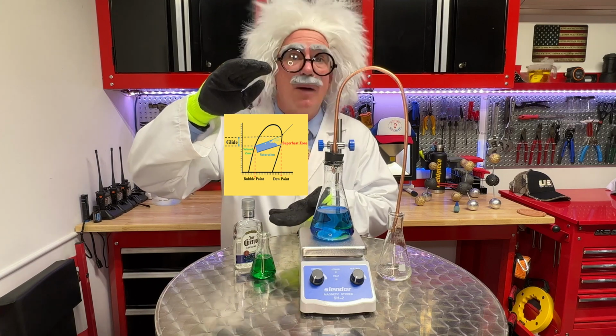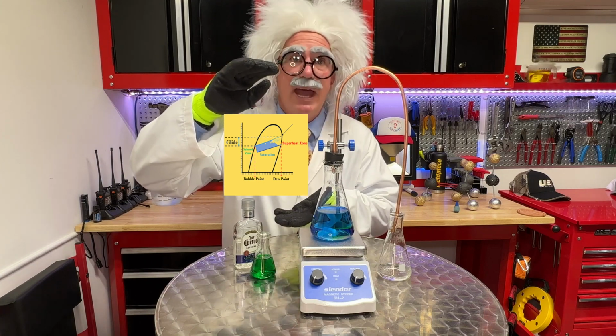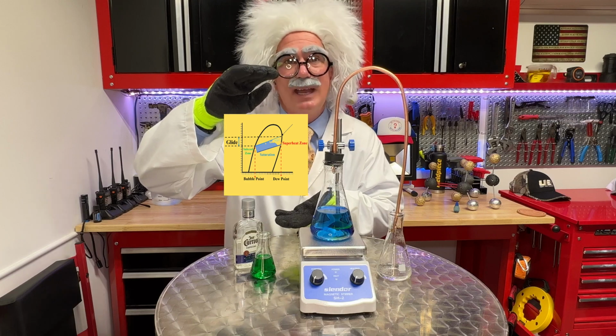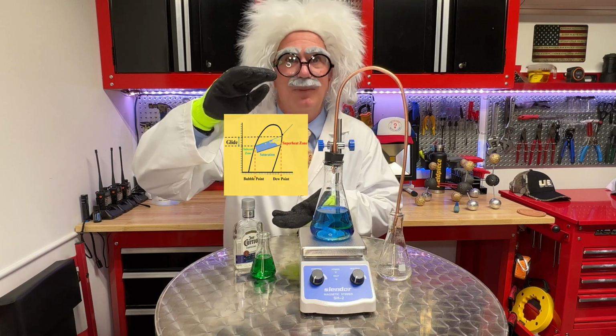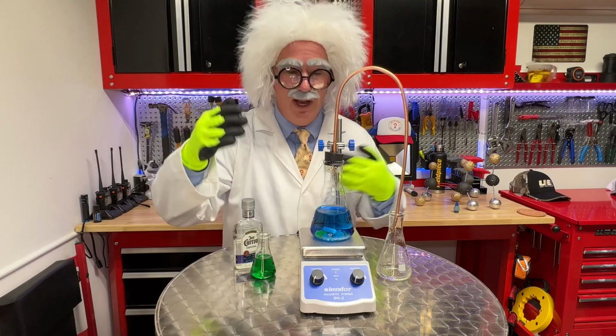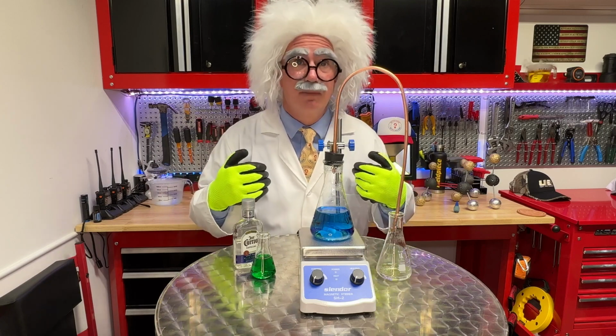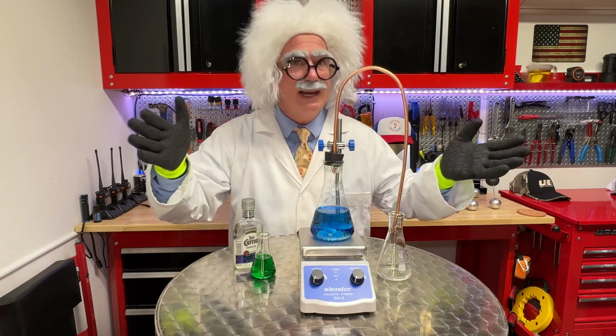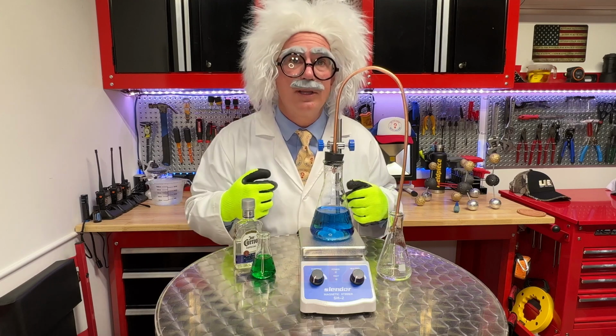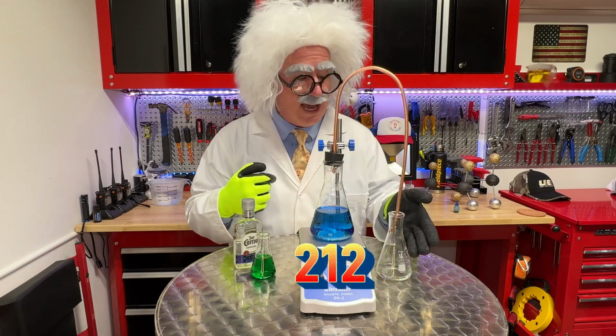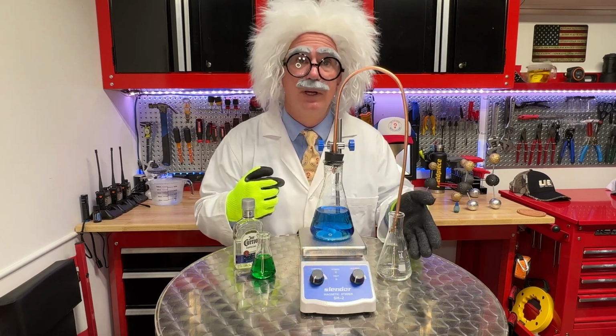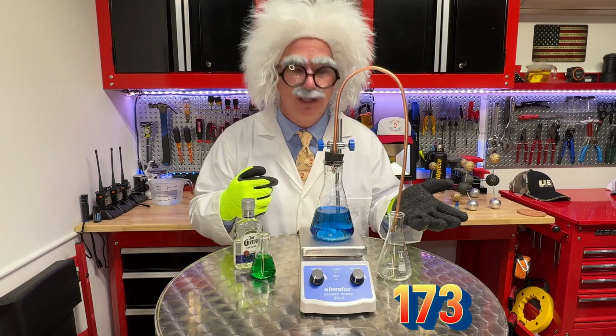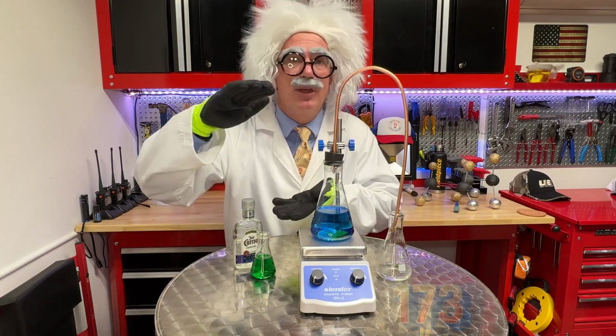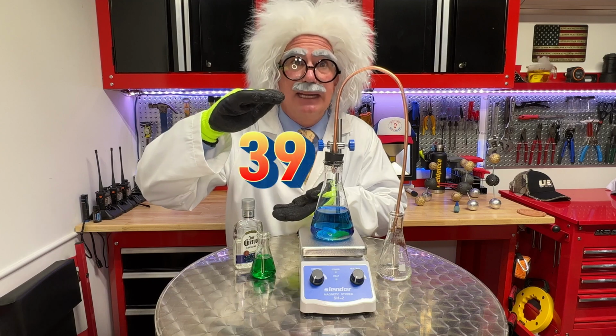And then down at our bubble, we know that everything below that is liquid. And so we use that when we're calculating our subcooling. So I hope you see that we have two different boiling points. At atmospheric pressure, we had water that would boil at 212.